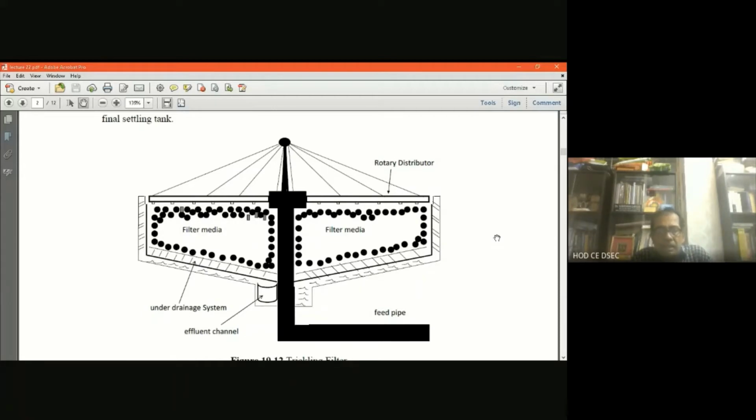where the bacteria are attached to that surface and the biofilm is produced, and there the water will be sprayed on the biofilm. So this is the basic terminology of the system, and the bacteria will degrade the organic matter, that is the carbonaceous organic matter, in the presence of oxygen. So it is an aerobic reactor, and since the bacteria exist on the attachment surface, that attachment surface is made of different materials that I will discuss in detail.